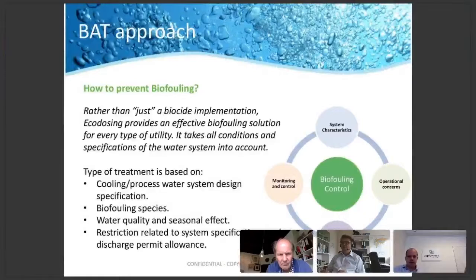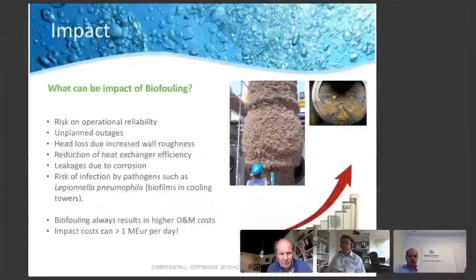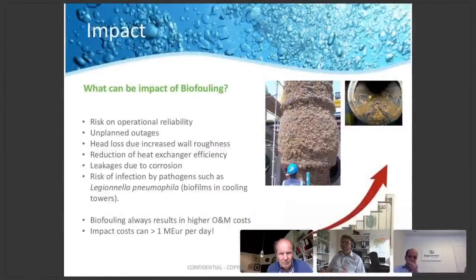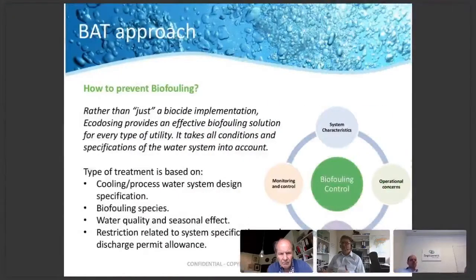The approach we use with Ecodosing is not just adding a biocide according to standard procedures to a seawater or cooling water system, but is based on the specific conditions of the system itself. Taking these specific conditions and characteristics into account, you can come up with a tailored approach, which is the best available technology.